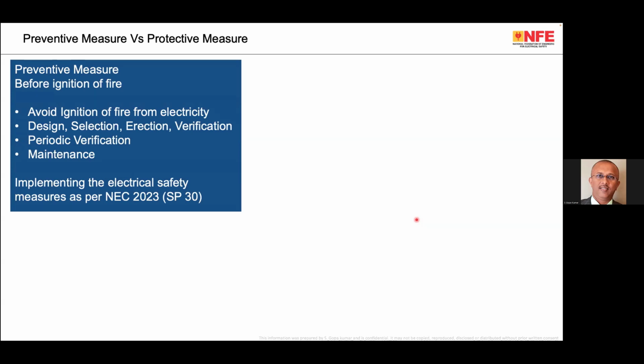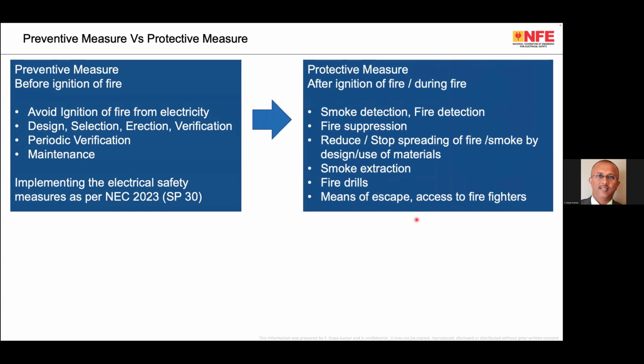So the temperature itself has to be limited by various measures so that the chance of ignition is reduced. Protective measures are after the ignition of fire. Protective measures such as smoke detection, fire suppression, and reduction measures for smoke or fire extraction, fire drills, means of escape, access. All these are protective measures, but after the fire. Whereas when we talk about thermal effect, we are talking about the measures which have to be implemented before ignition of fire from electricity.